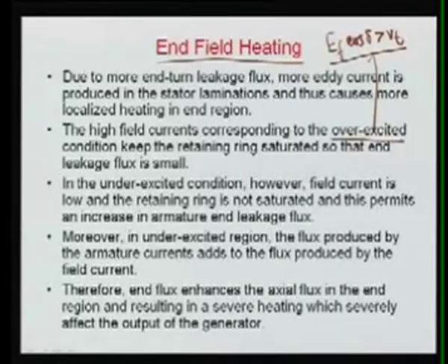Since here we are talking about the synchronous generator, the overexcited condition means this condition is satisfied. In that condition, the end rings normally get saturated and the leakage flux is small, so there is no heating problem due to the end field heating.